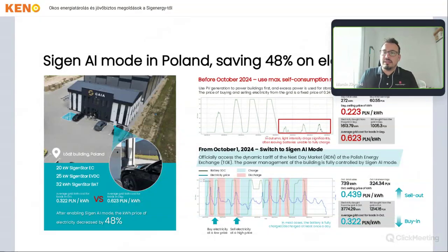What we found out was quite interesting: the system did nearly 46 cycles per month, so more or less one and a half cycles per day, generally between 1 and 2. Sometimes there was only one cycle, but generally it could do even 2 cycles per day, which was quite surprising when we started, and we couldn't fully understand why it was doing that.